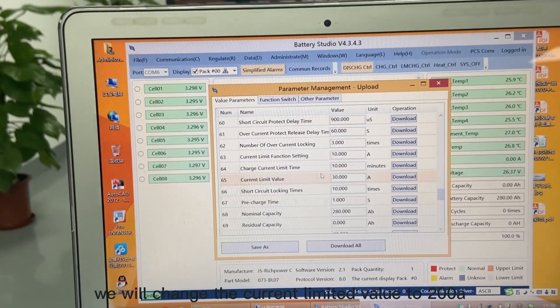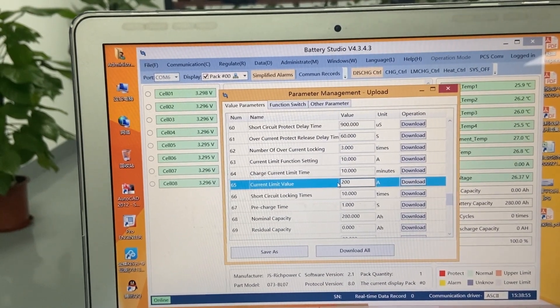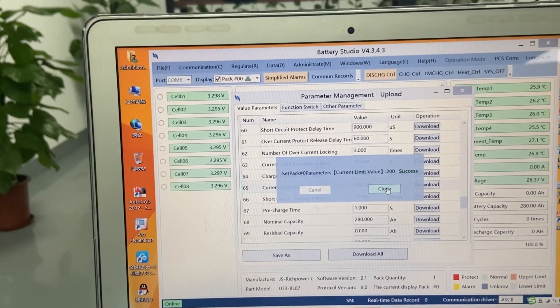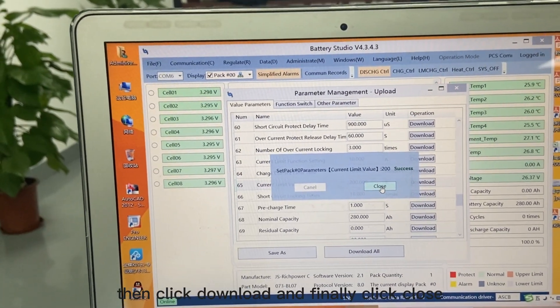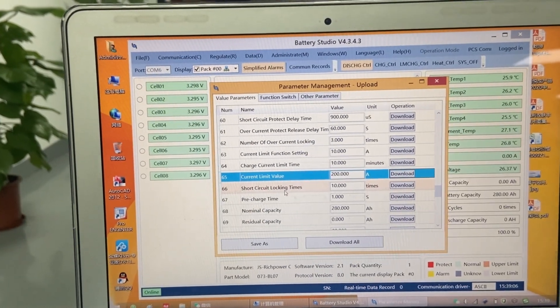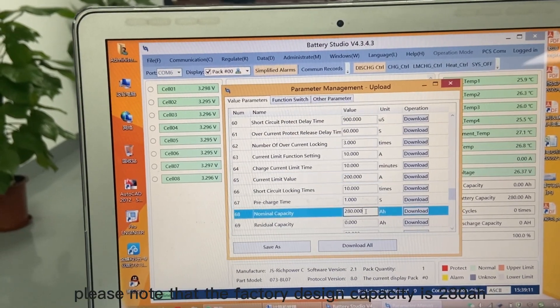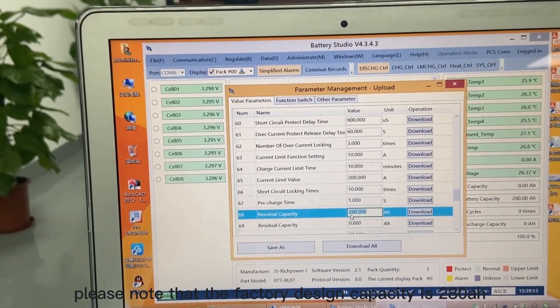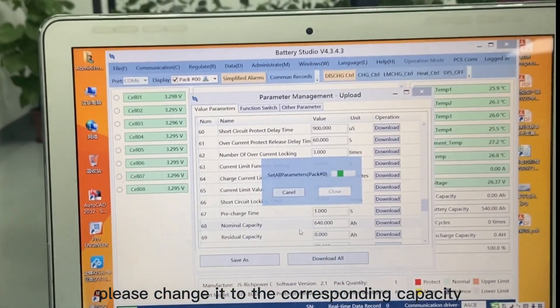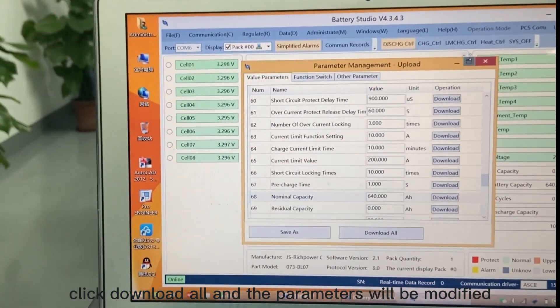We will change the current limited value to 200A. Then click download, and finally click close. We will also change the design capacity to 640Ah. Please note that the factory design capacity is 280Ah, so if you are not using this battery, please change it to the corresponding capacity. Click download all, and the parameters will be modified.